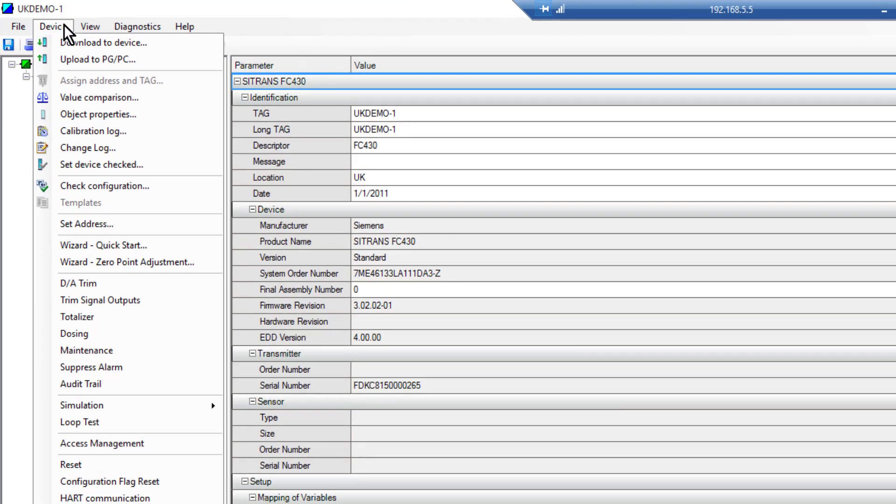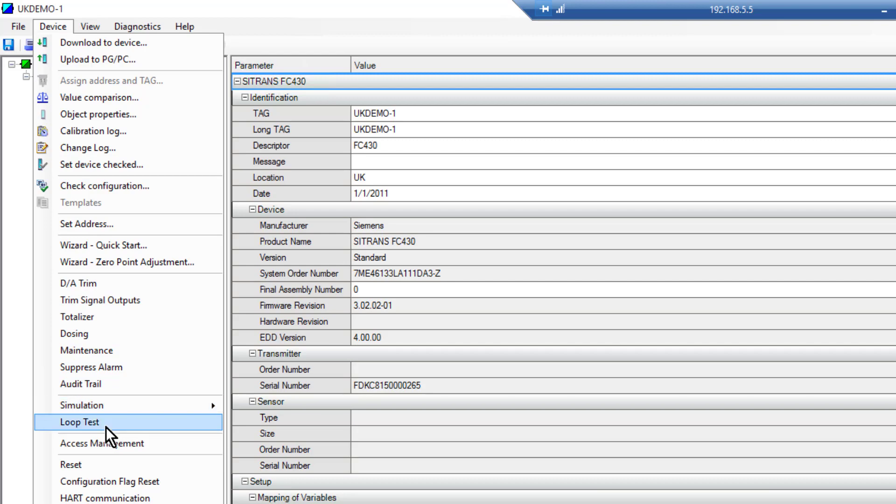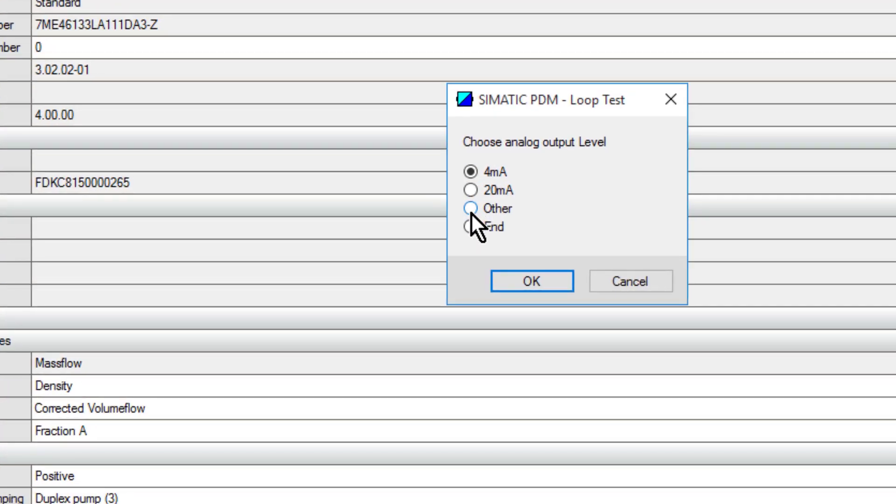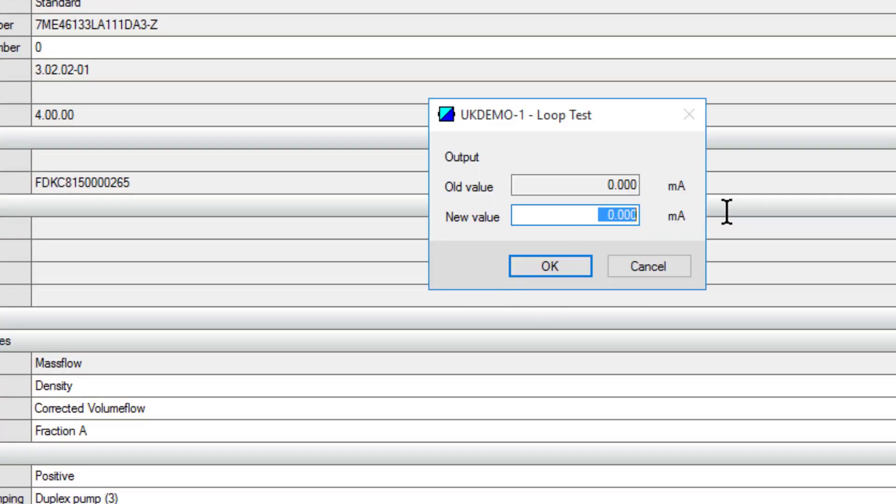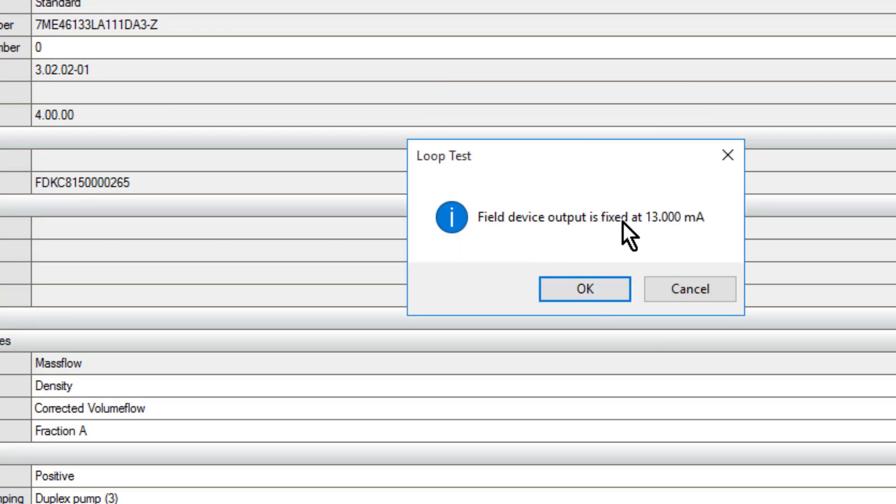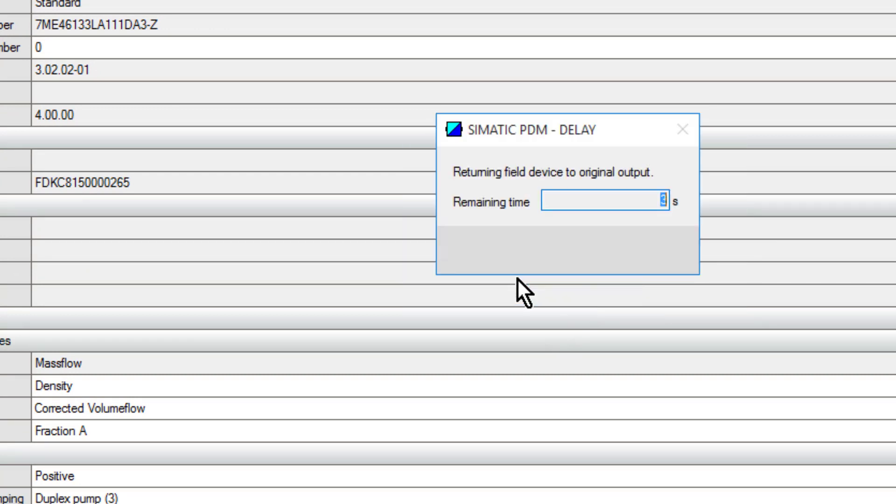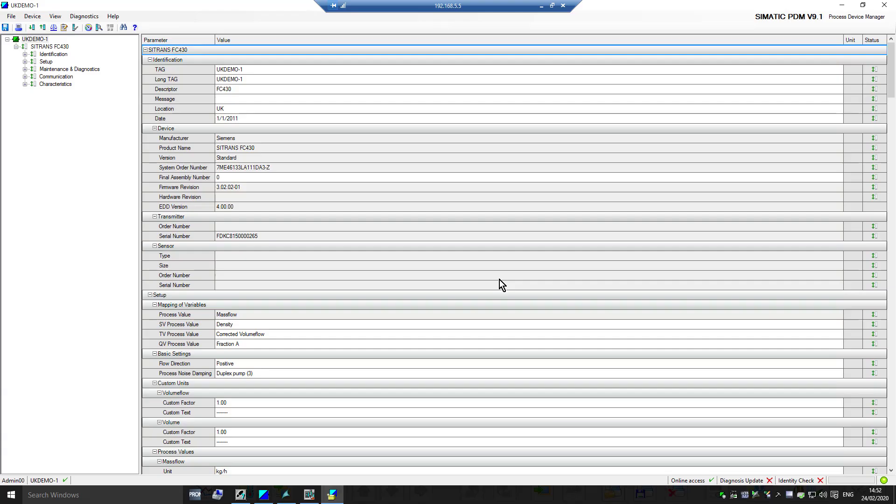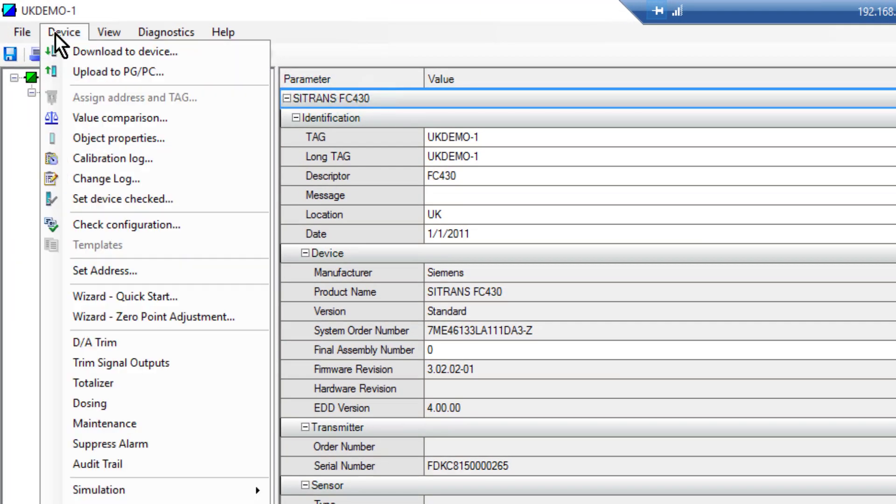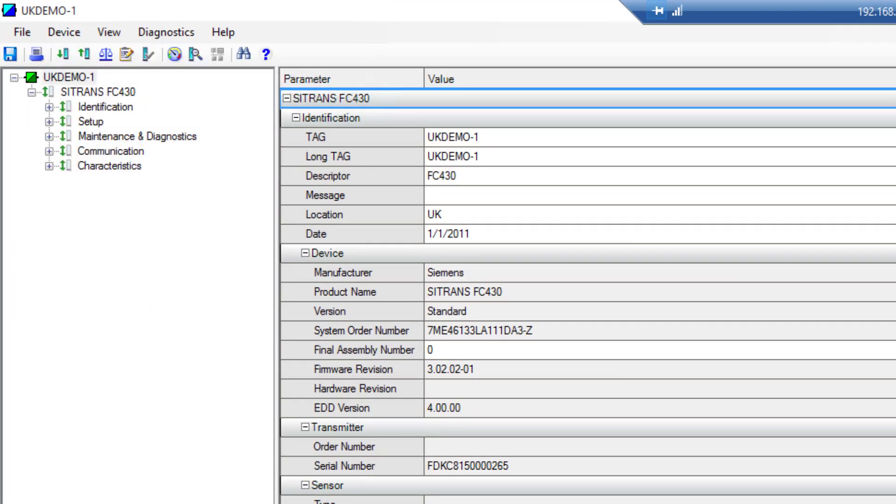The next thing you might want to do—if you had a handheld HART communicator, you might not be interested in programming this device, you just need to make sure it's wired up right and it's going to the right memory location on your DCS or SCADA. So we have loop test. Once I've done that, if I want to do a simulation, it's a little bit more than a loop test because it requires us simulating a flow value. I need to set the flow meter up, and to do that we'll use quick start wizard.